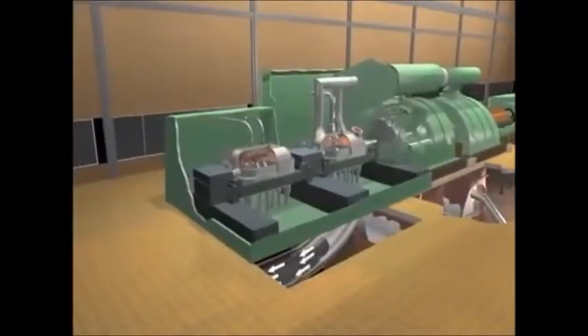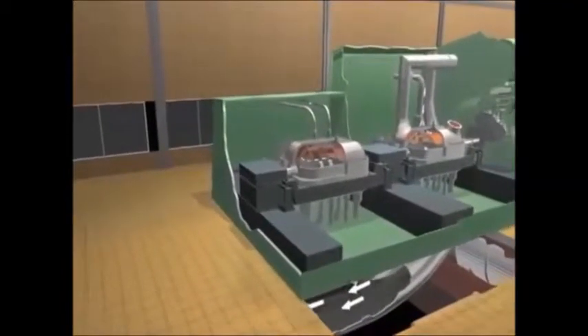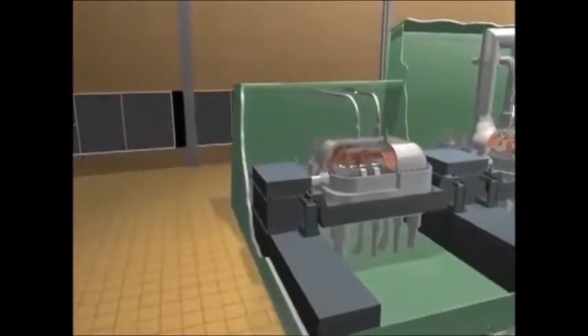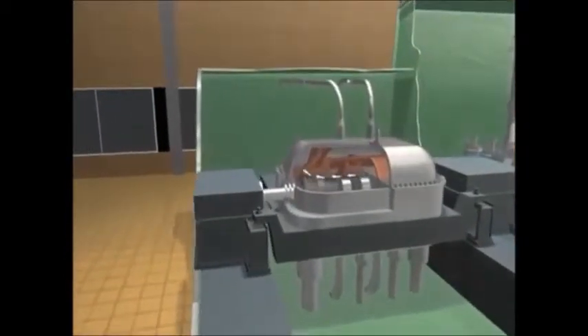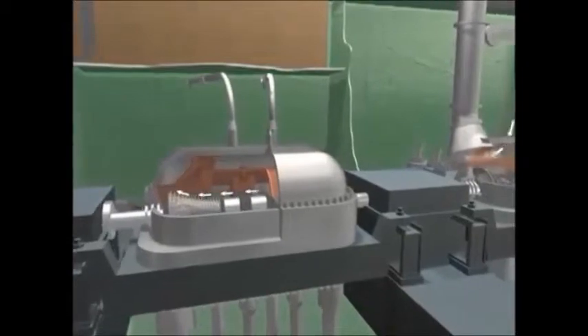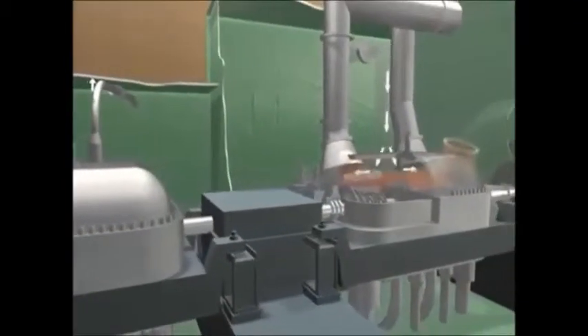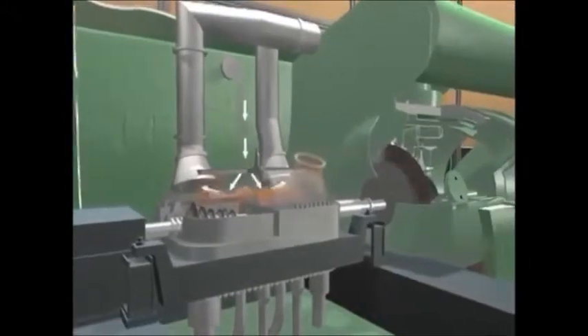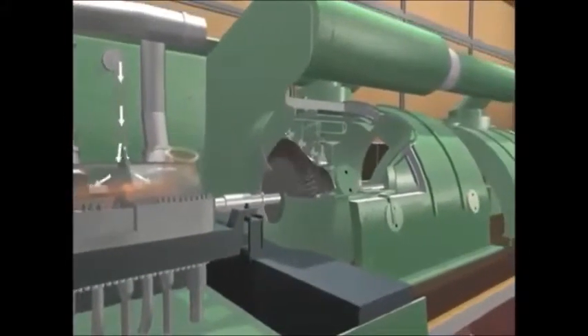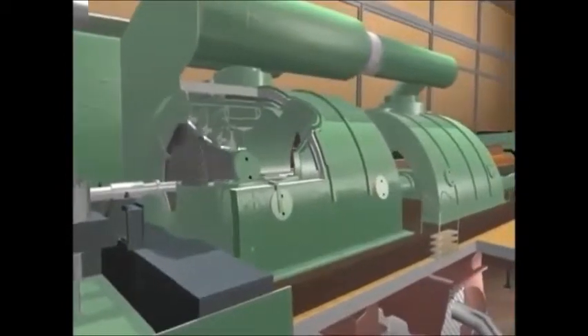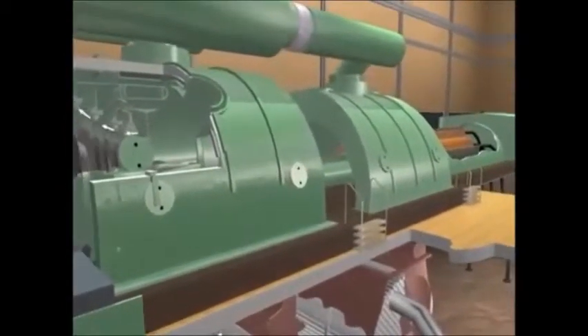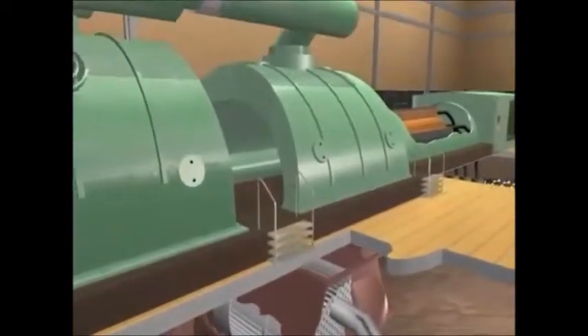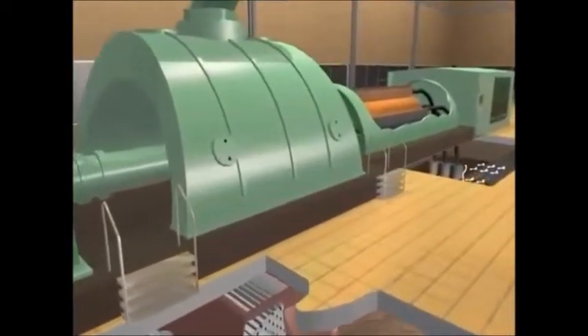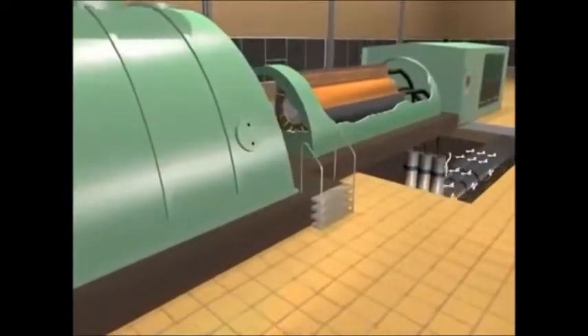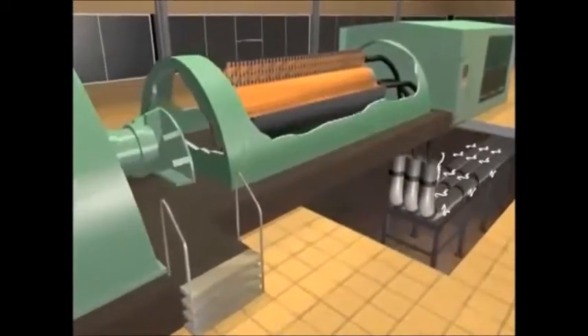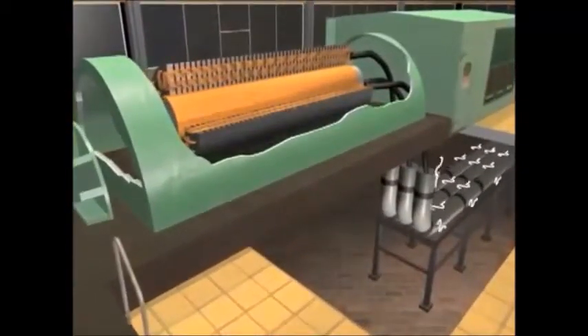High-pressure steam, now 1,000 degrees Fahrenheit at 3,500 pounds per square inch, is piped from the boiler to the first in a series of turbines. Here it expands between layers of turbine blades mounted on the turbine shaft. The steam loops back to the furnace, then onto the second turbine. In this process, the steam turns the series of turbines 3,600 revolutions per minute, providing power to the generator, the last in the series of machines. The generator continuously creates an electrical charge of 34,481 amps at 18,000 volts of electricity. From here, the electricity leaves the plant and begins its journey to customers.